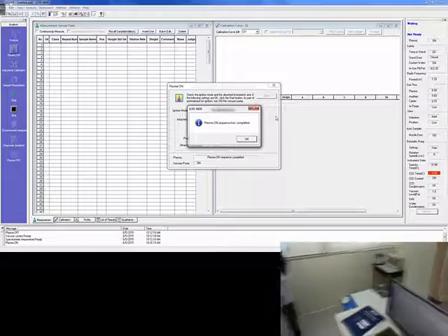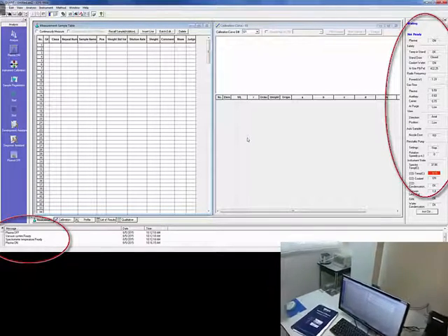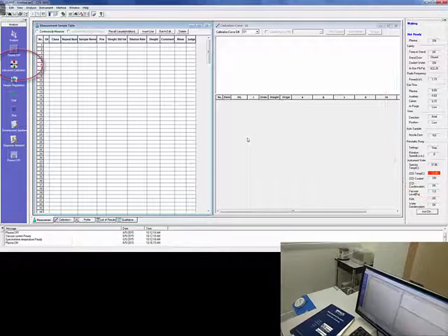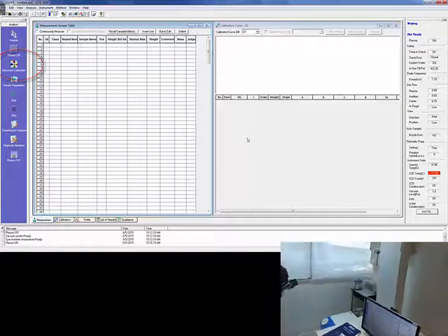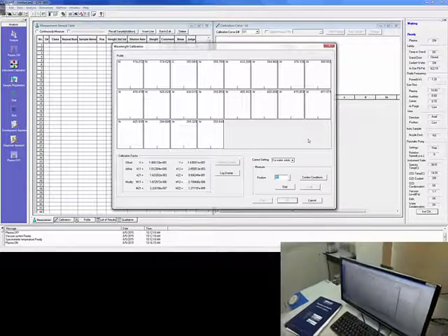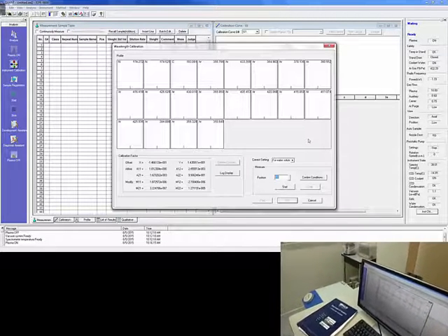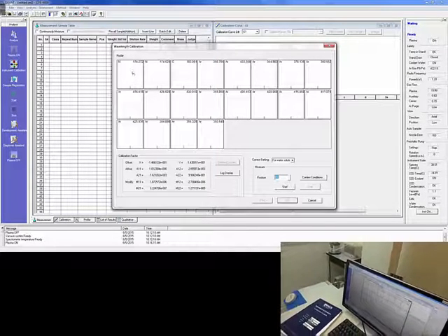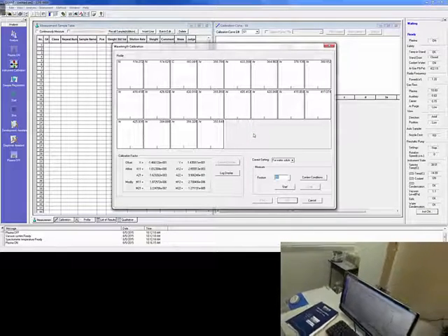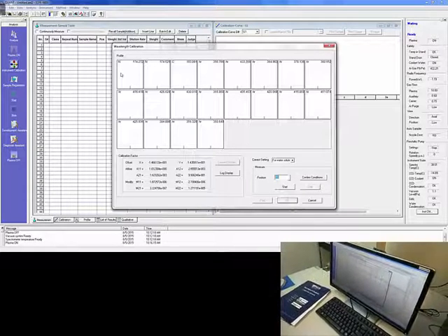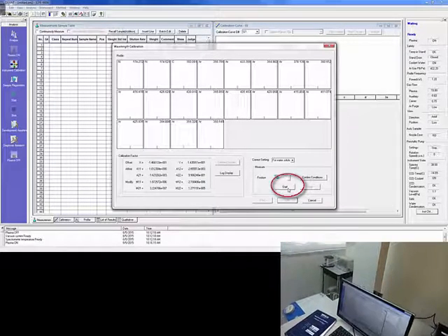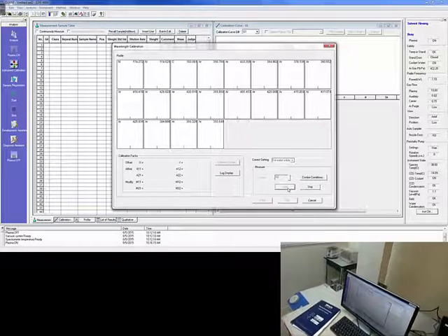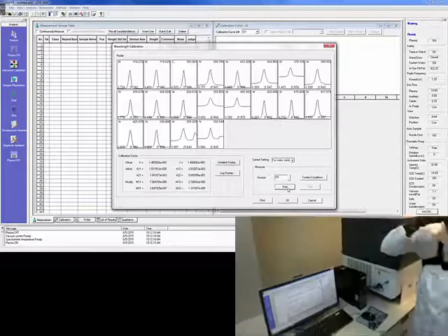Okay. So the first thing we need to do now that the equipment is running is to click instrument calibration and you should see a box like this coming up. Now, probably this needs to be done just once a day at the beginning of the day when you're starting. There's nothing here for you to actually do in terms of—this has already been set up and it uses emission lines from these elements, nitrogen and argon, to actually do the calibration internally on the instrument. All you need to do is press start and this will take maybe a minute or two and that just sits. There's nothing for you to do. It will just sit there and do that.